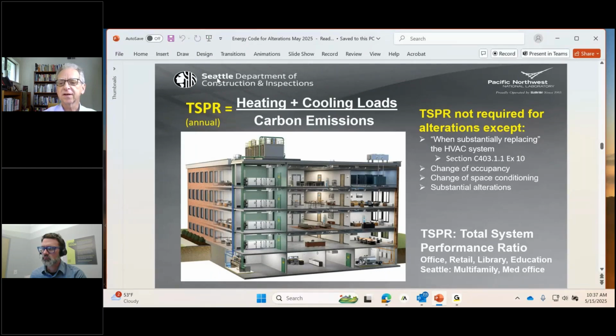This is all done through a software system that's free and available online, so they can track these. I just learned that 19%, about 1 out of 5 projects, fails the first time through, and they have to go back and make changes to bring the overall efficiency up to where it should have been. So it is taking effect. Sometimes you have to use larger ducts to get your fan size down or something like that, and that'll bring you within bounds.